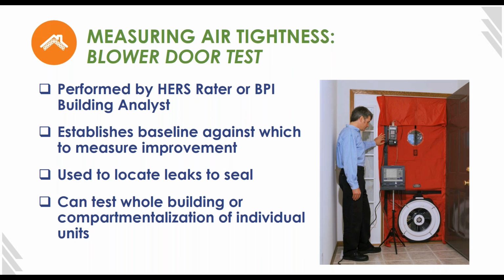What this does is establish a baseline against which we can measure improvement. You pressurize or depressurize the building, establish how tight it is, how much air leakage there is at a particular pressure. You can also do some visual verification of air leakage using things like a smoke pen, or sometimes just putting your hand against the wall in areas where you might have air leakage — you can actually feel the air movement.